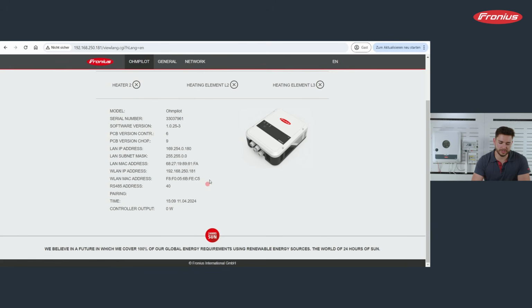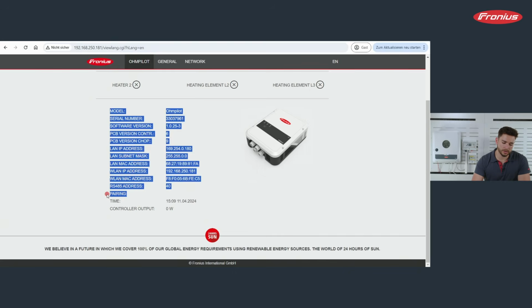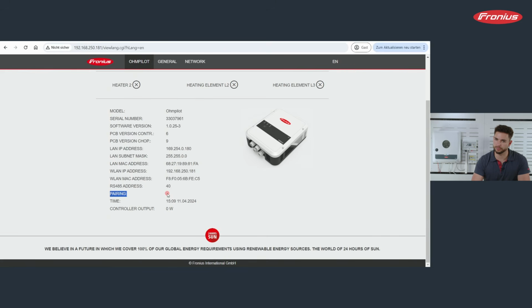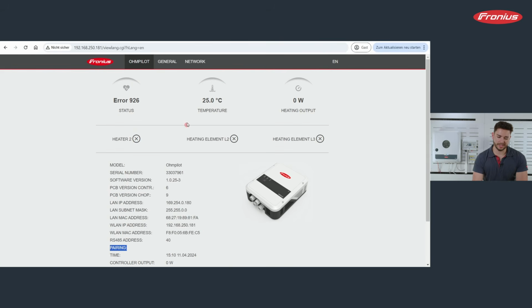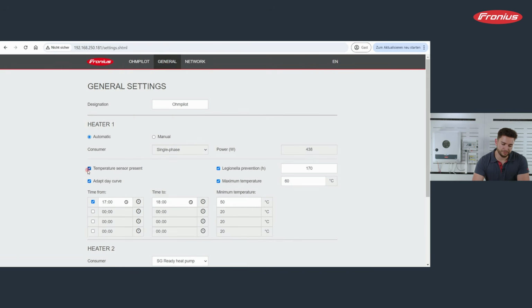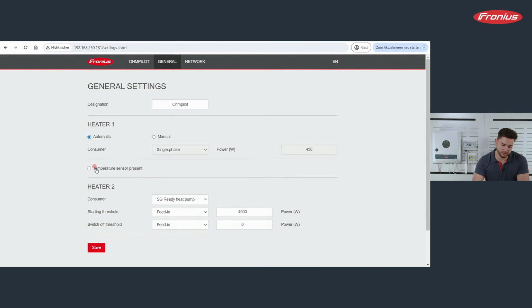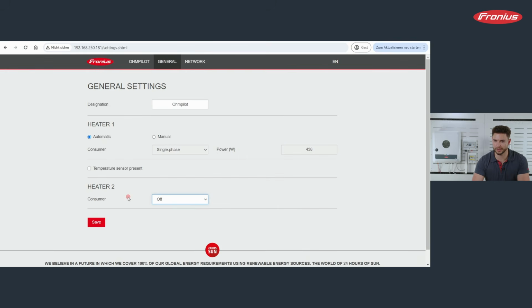Further down below, there is a list of some interesting information, such as the pairing. So after we have done it correctly, we should read here on pairing the serial number of our inverter - if done correctly, this should be set up here. Now, this is the first screen. The second screen is the more interesting one, on the submenu General. If we go there, we have all the settings, and I quickly set it to standard. So this is what you have when you first connect to a brand new Ohmpilot: you have designation, which you can rename if you want, and you have the heater number 1 on automatic.